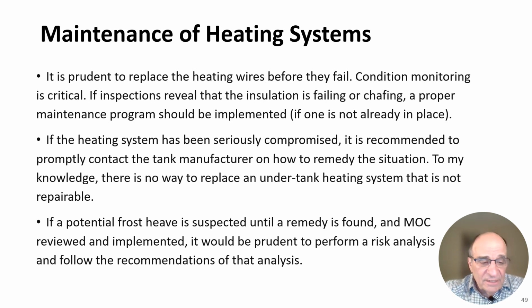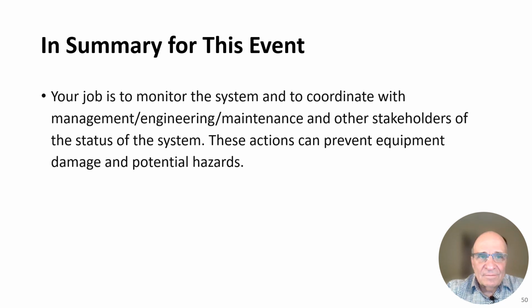If potential frost heave is suspected, until a remedy is found, an MOC must be reviewed and implemented. It would be prudent to perform a risk analysis and follow up on recommendations from that risk analysis to make sure that you don't end up having frost heave taking place. In summary, for this event, your job is to monitor the system and to coordinate with management, engineering, maintenance, and other stakeholders on the status of the heating system. These actions can prevent equipment from being damaged and prevent potential hazards.